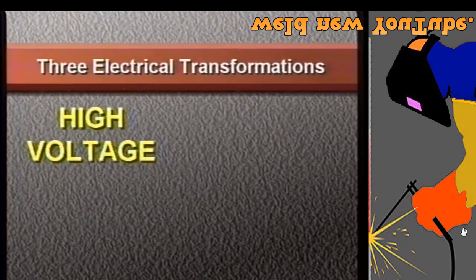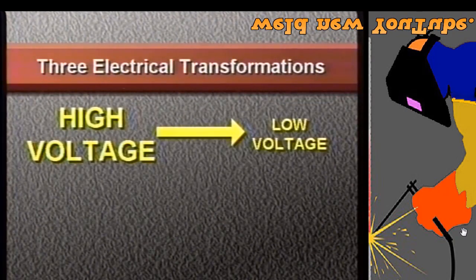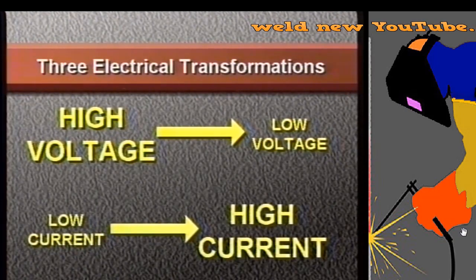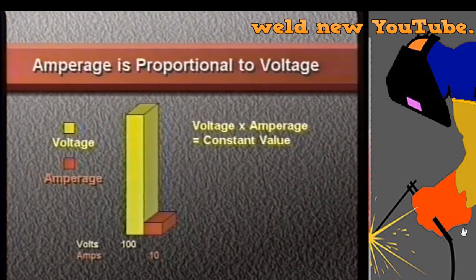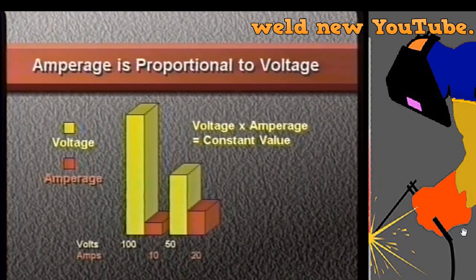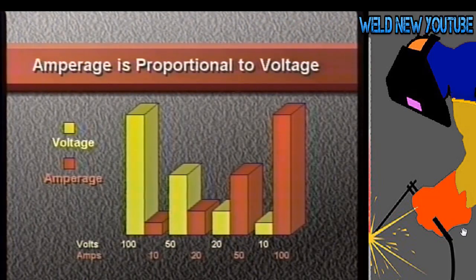Let's take a look at the three electrical transformations that occur inside a traditional arc welder. First, high voltage is reduced to low voltage, both to meet the requirements of the welding process and for safety reasons. Simultaneously, the voltage reduction proportionally increases the current, or amperage, from the much lower current power source. The relationship between voltage and current is simple: a power source of 10 amps at 100 volts can be converted to 20 amps at 50 volts, or 50 amps at 20 volts, or 100 amps at 10 volts, given the right electrical devices.